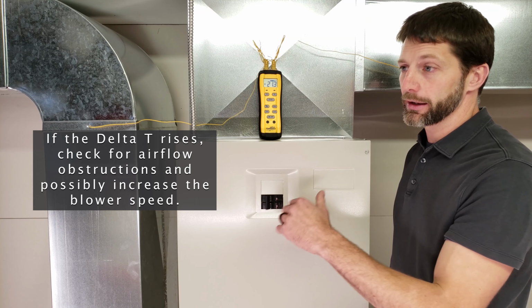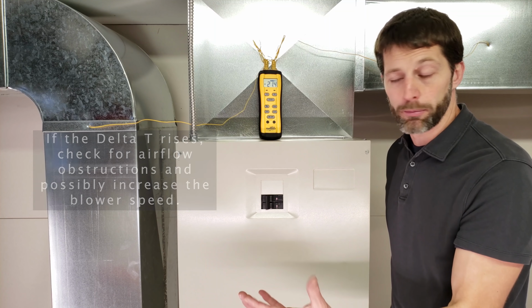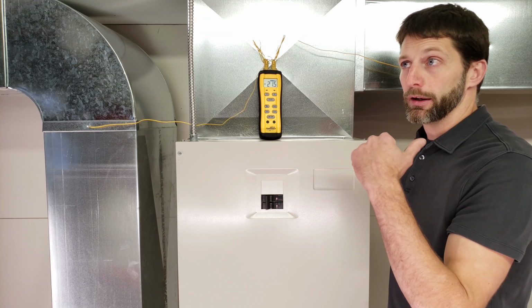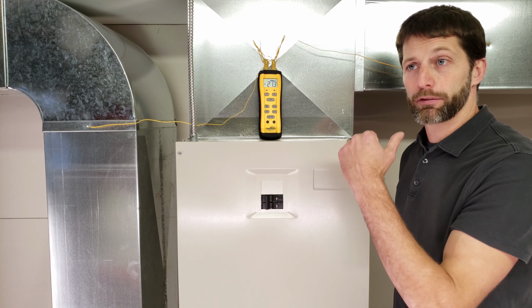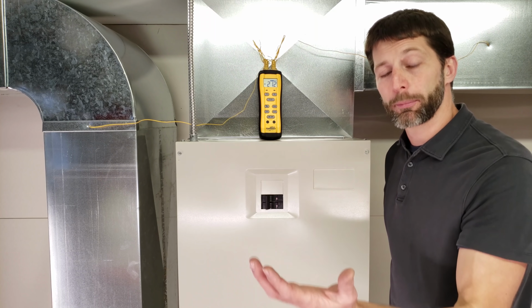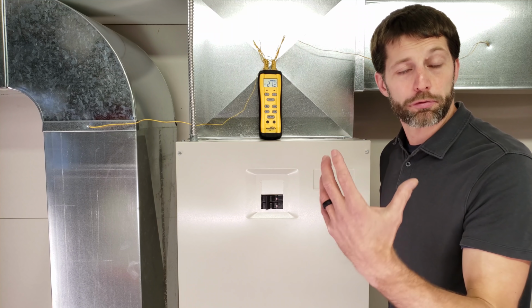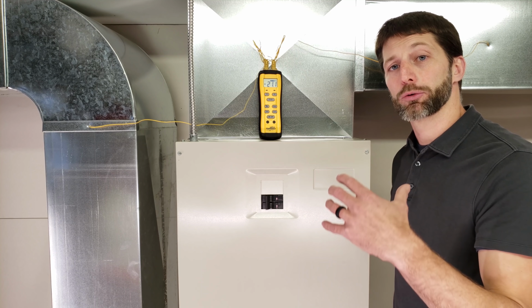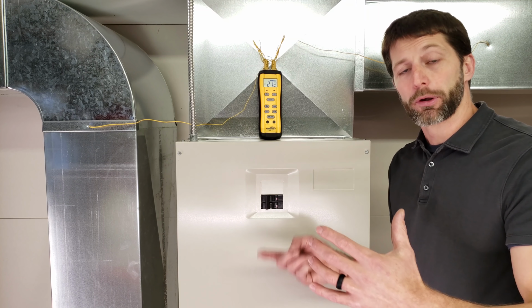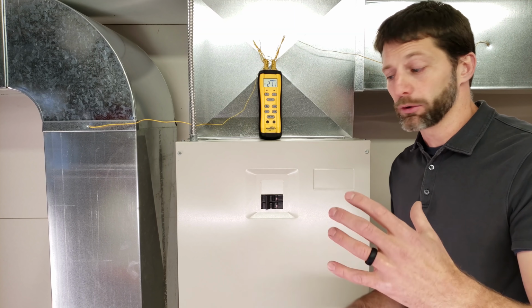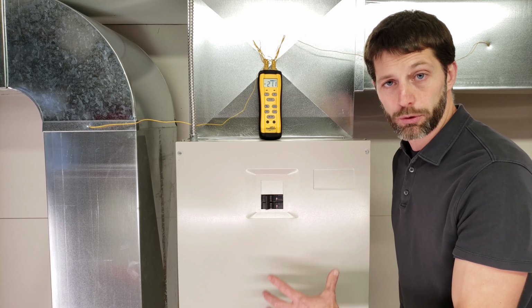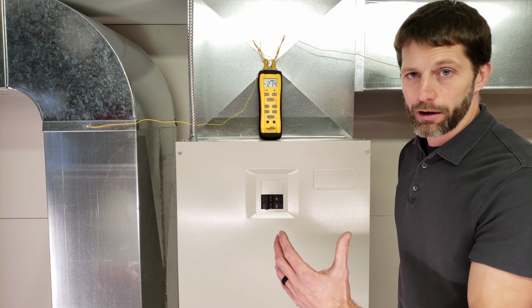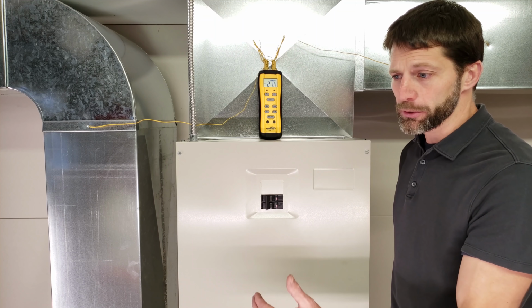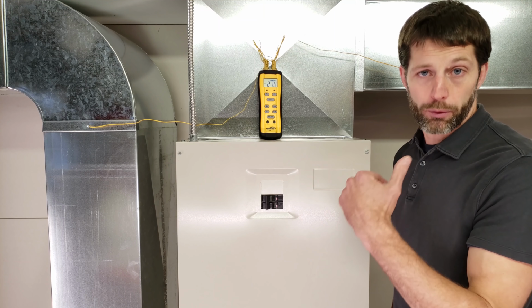So that's different than if you had a heat pump running in heating mode without the electric strip heating. That's going to vary greatly. The delta T is going to vary greatly depending on the outdoor temperature and if the outdoor coil has frost on it. So you've got to remember that the outdoor coil, the refrigerant flowing through there, has to absorb the heat there in order to reject the heat at the indoor unit. So you're not going to have an exact temperature for the delta T for what that should be.